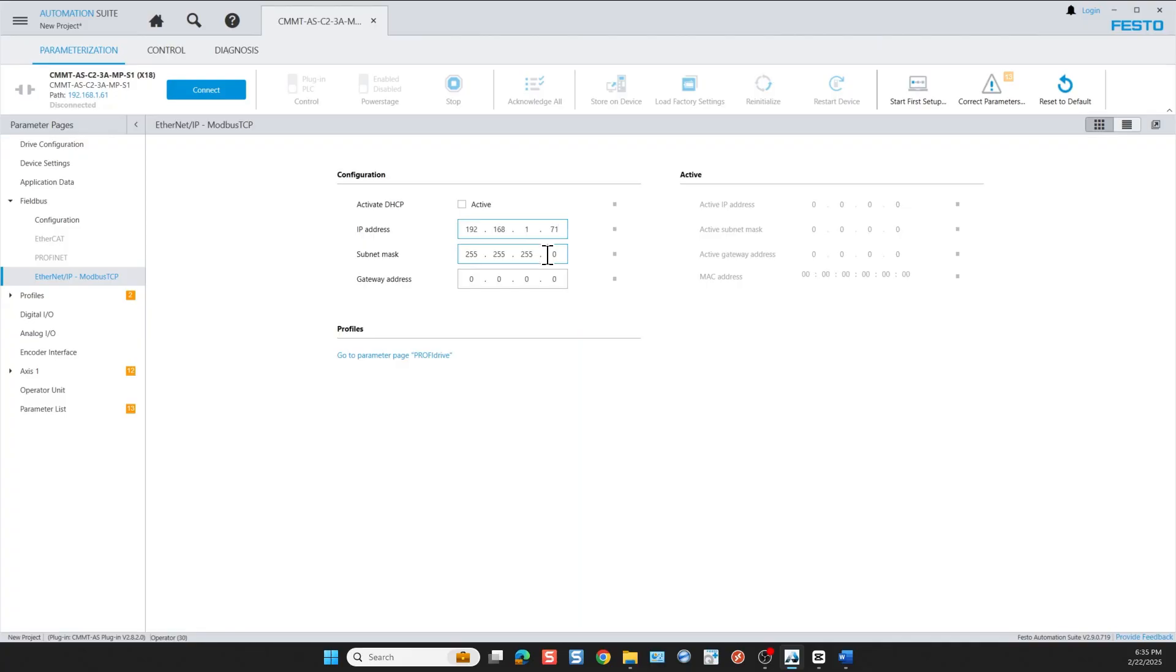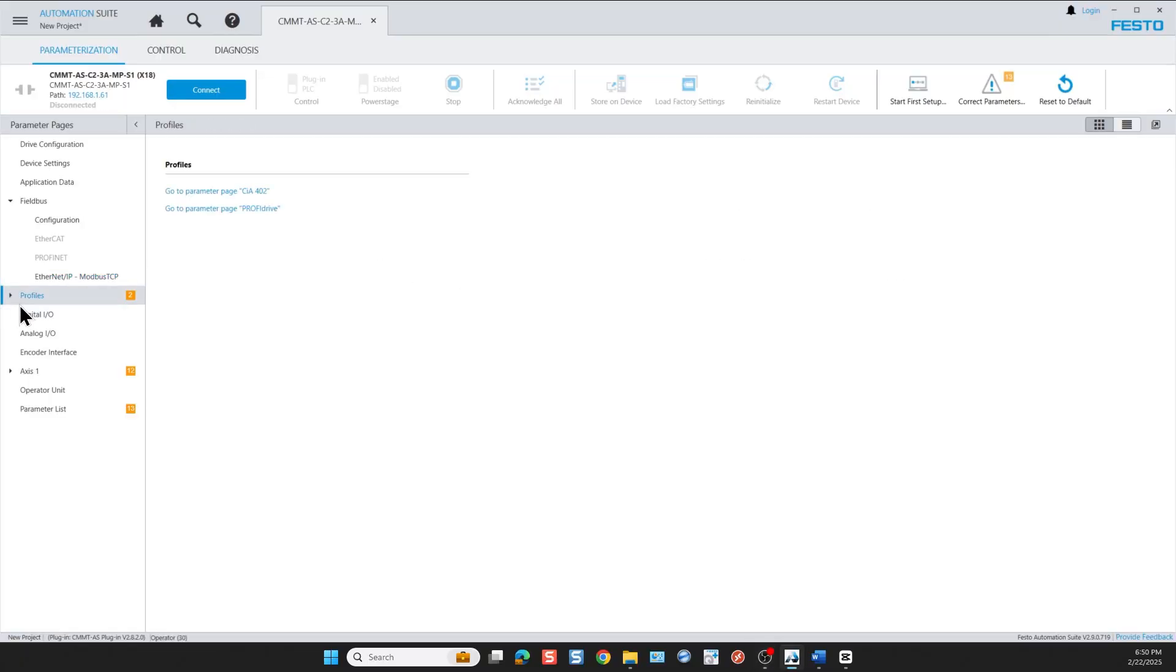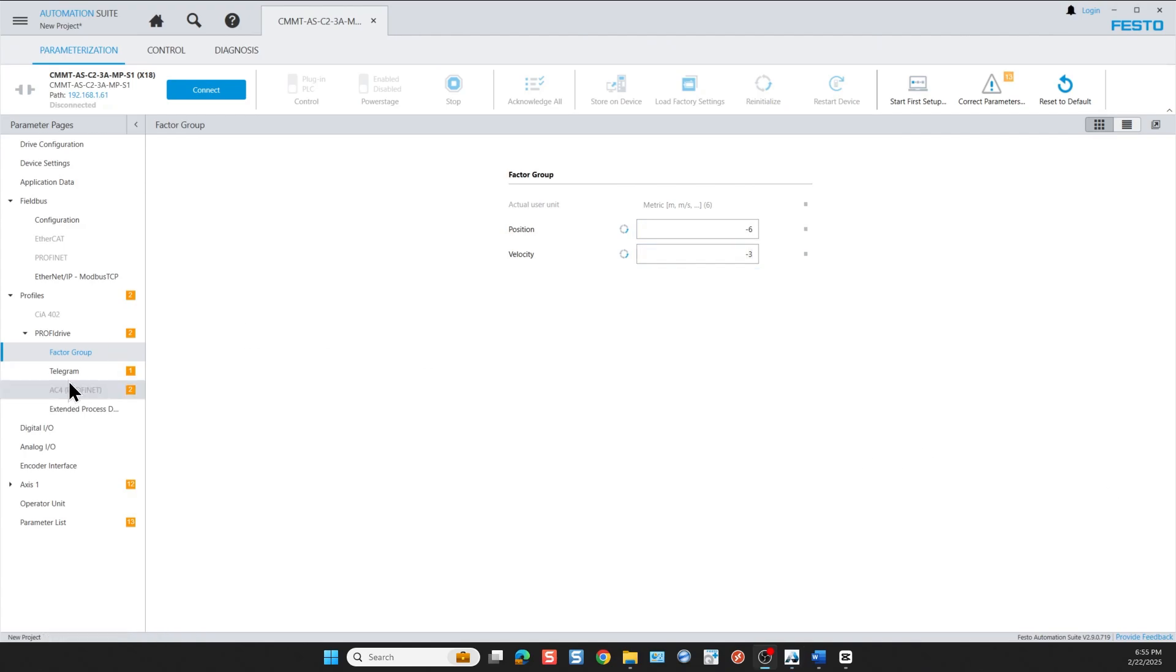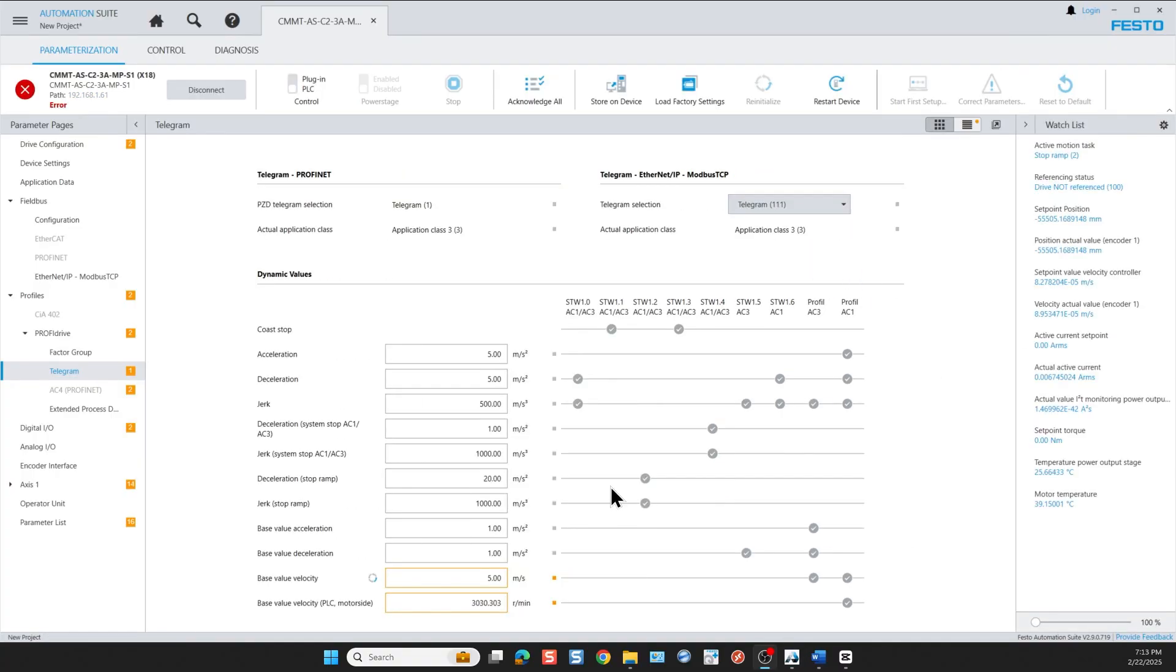Next we move on and configure the profiles. We start with the factor group. In the factor group we have two parameters that we need to configure: the position and velocity resolutions. We have six decimal places for position and three for velocity. We leave the defaults unchanged. And then we have the telegram selection. For point-to-point positioning library we use telegram 111.